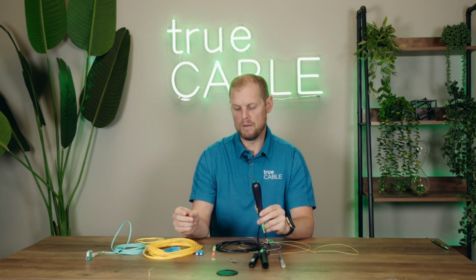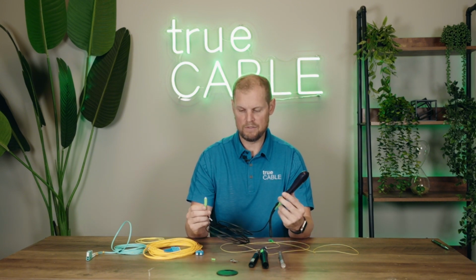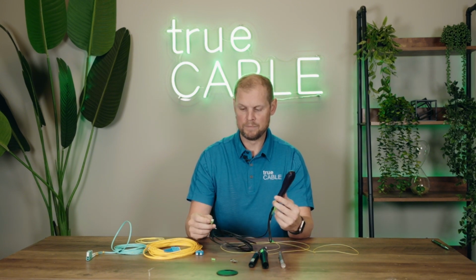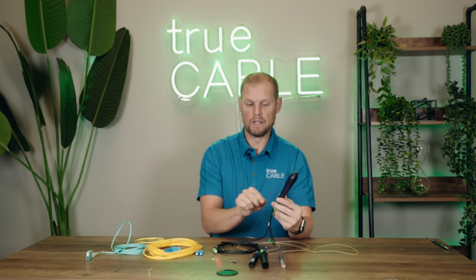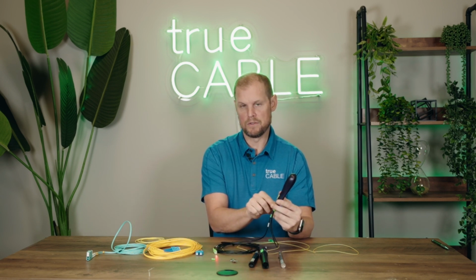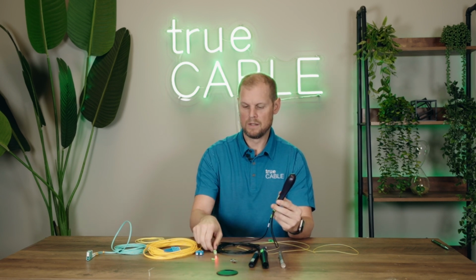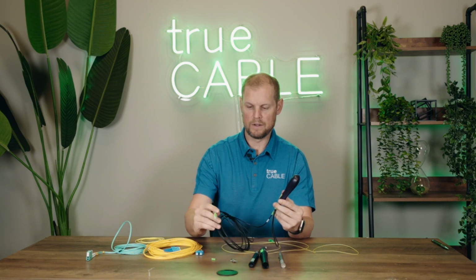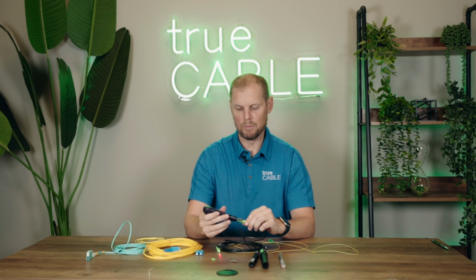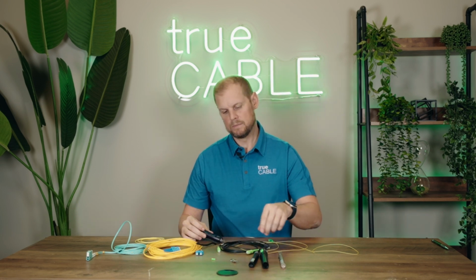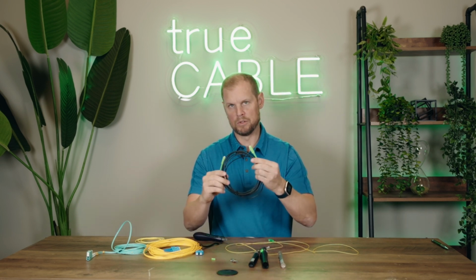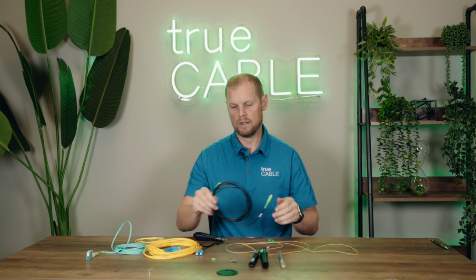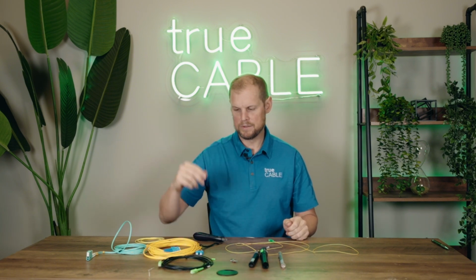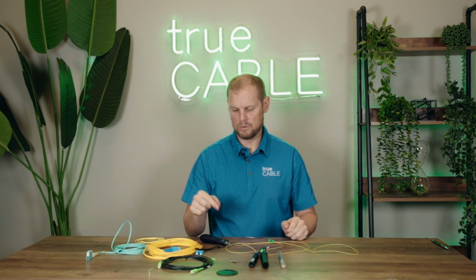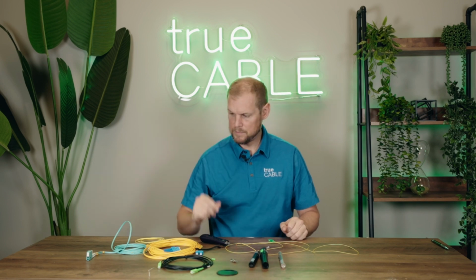So 9 times out of 10, when diagnosing a fiber optic cable that has a black jacket, you're simply looking at the connector end to verify there's no light being lost out of the connector, and looking at the far end connector to verify there's no loss there. It's a little limited with a black cable jacket, but luckily black cable jackets are less common in data center and enterprise indoor applications where these VFLs are typically used.